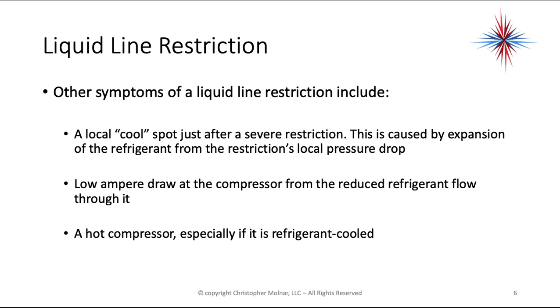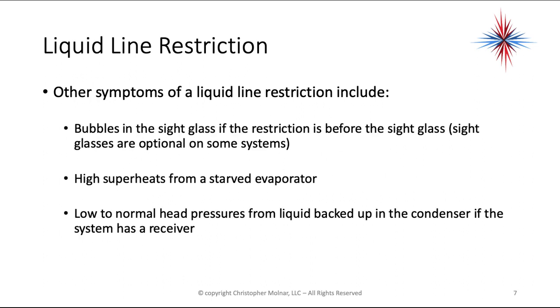Other symptoms of liquid line restrictions include a local cool spot just after the severe restriction, caused by expansion of refrigerant from the pressure drop. Low amp draw at the compressor from reduced refrigerant flow through it. A hot compressor — especially since most compressors are refrigerant-cooled. Bubbles in the sight glass if the restriction is before the sight glass. High superheats from a starved evaporator. Low to normal head pressures from liquid backed up in the condenser if the system has a receiver.